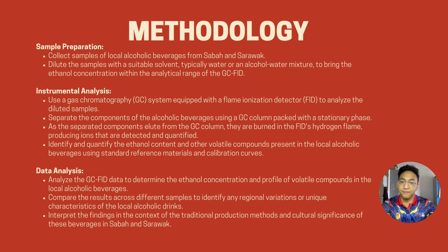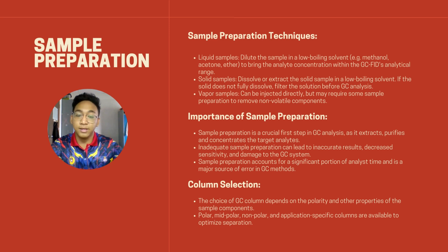For a liquid sample, dilute the sample in a low boiling solvent to bring the analyte concentration within the GC-FID analytical range. For solid samples, dissolve or extract the solid in a low boiling solvent and filter the solution before GC analysis. Vapor samples can be injected directly but may require some sample preparation to remove non-volatile components. Proper sample preparation ensures accurate results, high sensitivity, and minimizes the risk of damage to the GC system.